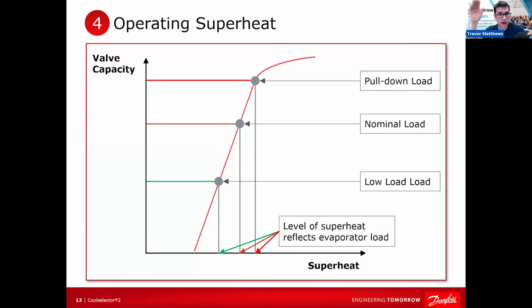So if you ever have a lot of hunting and you made sure that it's not your condenser fans banging on, banging off, or your evaporator fans changing, or someone's opening the door, changing the load very quick, and it's a stable load, the coils are clean, everything's running normal, and you got that happen. Increase that superheat just 1 degree, you know what I mean? And then another degree. And then all of a sudden you'll see that line start to stabilize. I love that. I love that.